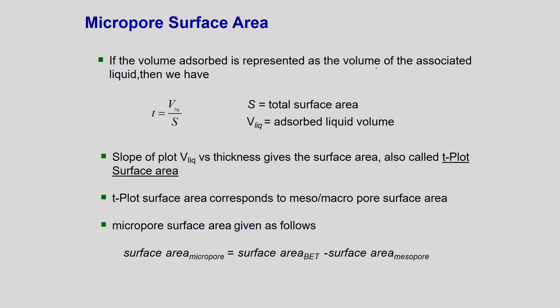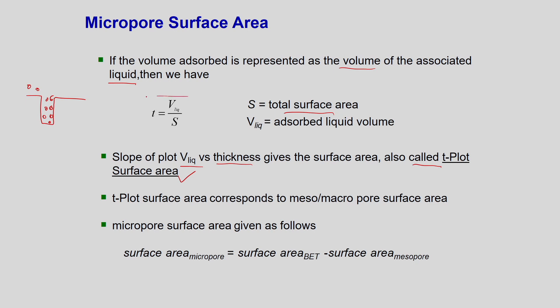If the volume adsorbed is represented as the volume of the associated liquid — assuming all nitrogen molecules in the gas phase are representing liquid — then the thickness is given by the ratio of liquid volume to the monolayer. The slope of the volume versus thickness plot will directly give you the surface area, also called the t-plot surface area, because it is related by this expression.